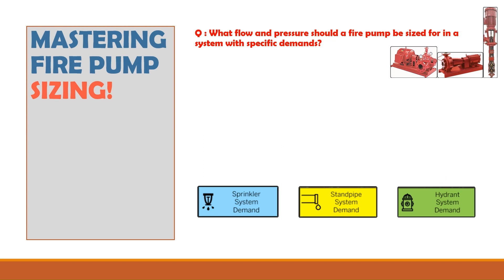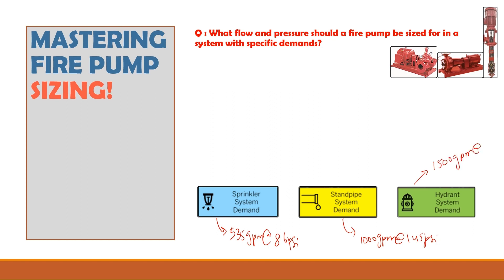Based on hydraulic calculations, the sprinkler system demand is 535 gpm at 86 psi, the standpipe system demand is 1000 gpm at 145 psi, and the hydrant network demand is 1500 gpm at 20 psi at the most remote hydrant.